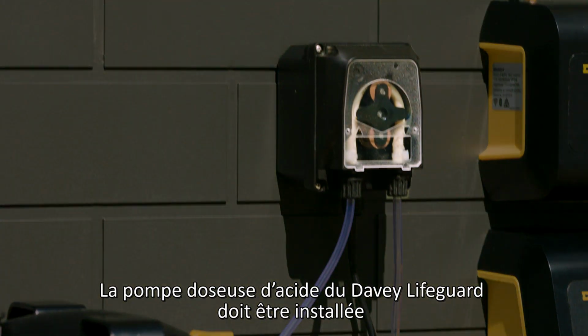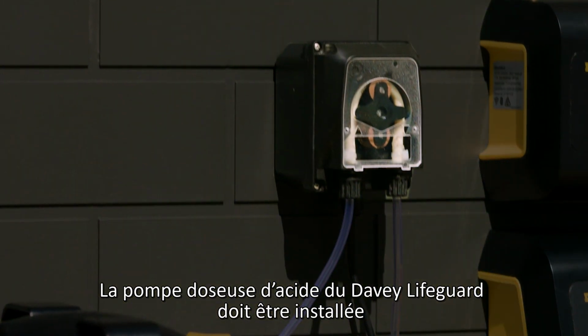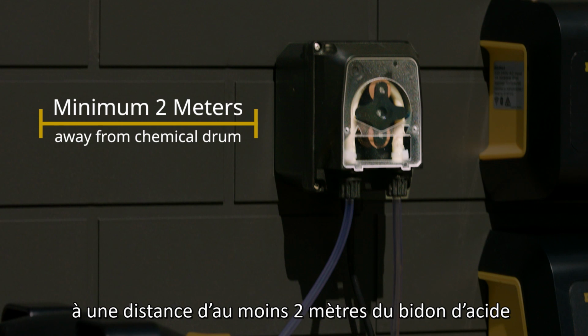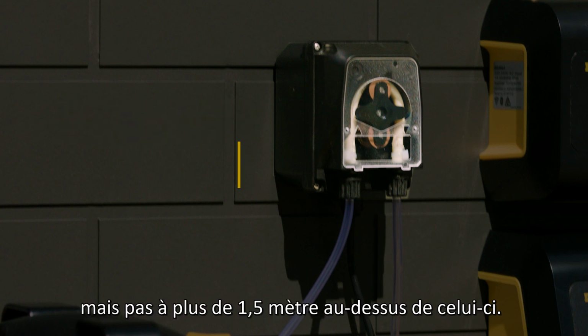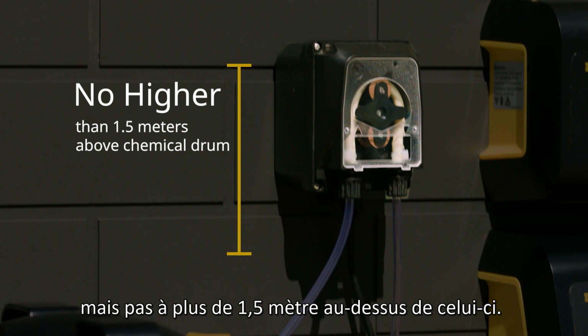The acid dosing pump on the Davey Lifeguard needs to be installed a minimum of 2 metres away from the chemical drum, but no higher than 1.5 metres above it.